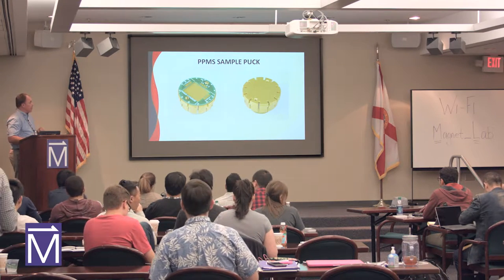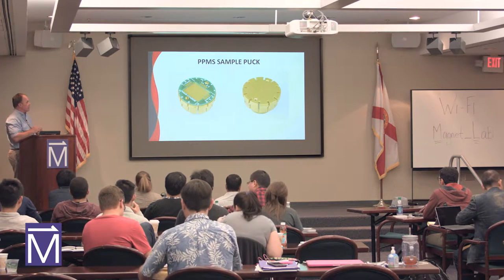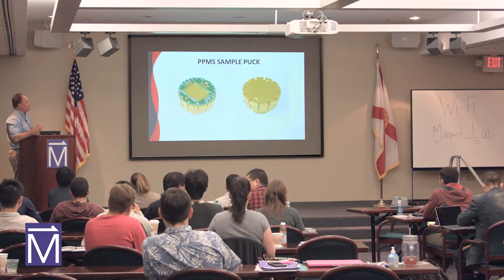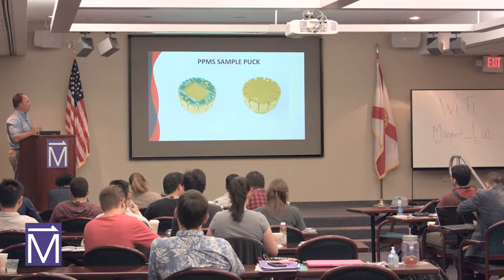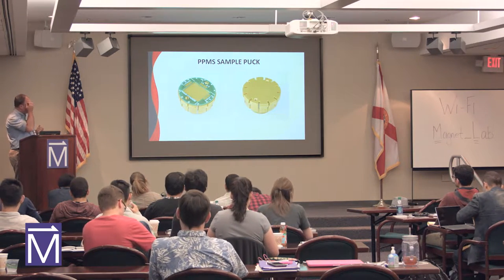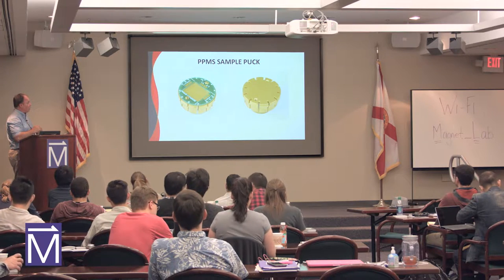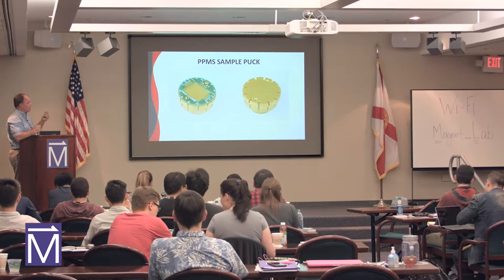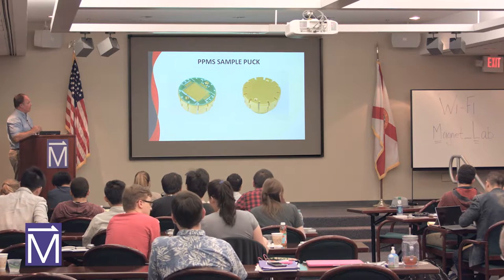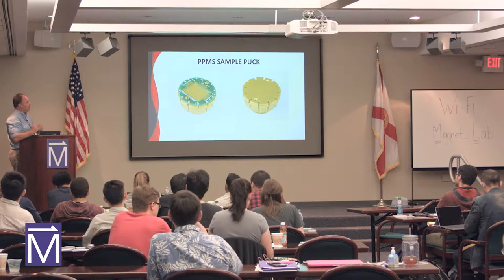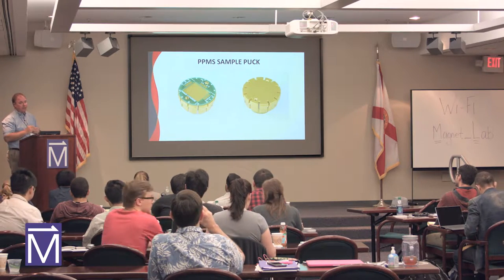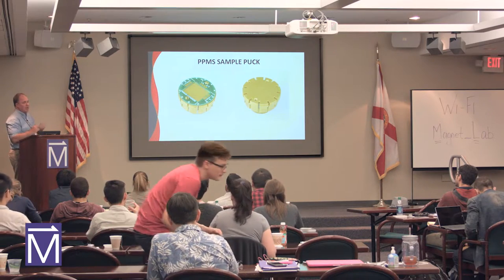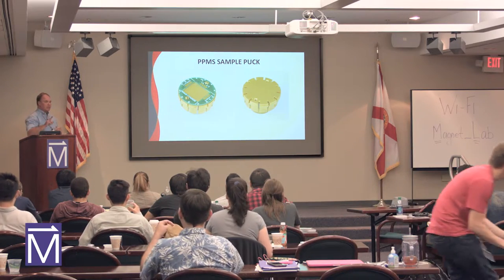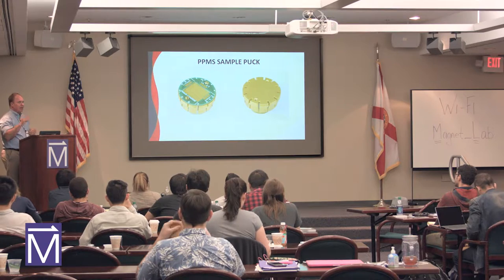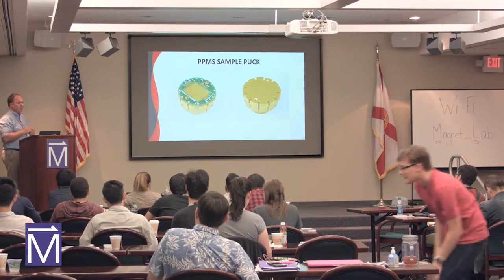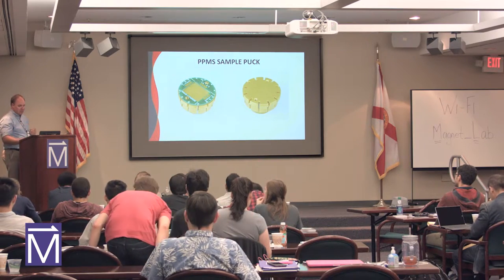Another picture of the sample puck. One of the sample pucks has a printed circuit board on it with some numbering. You can put three samples on it because of the 12 wires, so you can do three- and four-wire measurements. There's actually another puck that lets you put your own wiring on it, so you can make your own connections to any of the pinouts. But they're twisted pairs, so 1 and 2 are twisted pairs, 3 and 4 are twisted pairs, up to 12.